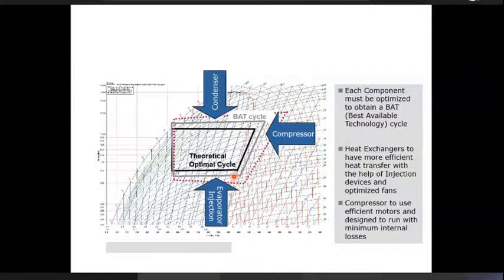Then we have looked at this from a refrigeration perspective, but a compressor will also require a motor, an electrical motor that will be driving this compressor. For smaller systems, it is common to use hermetically sealed systems. The residential products that we buy today would have a hermetically sealed compressor, which means the motor is enclosed in a way that there is no shaft seal requirement. The electrical motor is enclosed fully in a shell where the compression process is taking place, and we also make use of refrigerant to cool the motor.